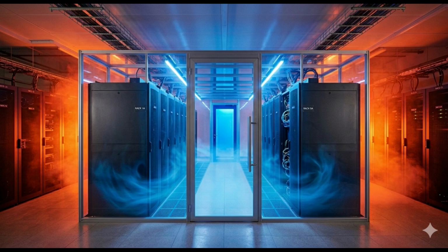It is, because now your server intake temperature starts rising rapidly. The server's internal logic detects the heat, so it commands the internal fans to spin even faster to compensate. Which just demands more air, pulling an even harder vacuum, sucking in even more hot air. A textbook destabilizing positive feedback loop. Within minutes, you can have rapid overheating and thermal shutdown of the IT equipment.